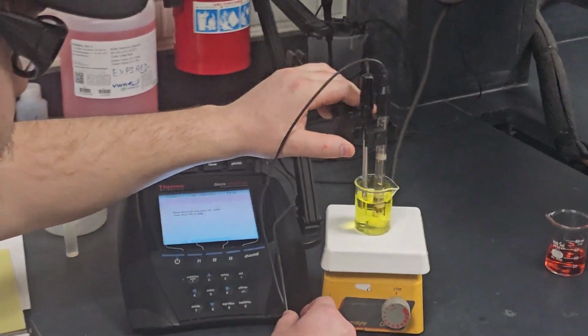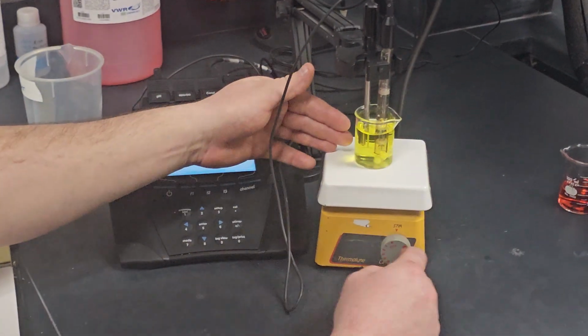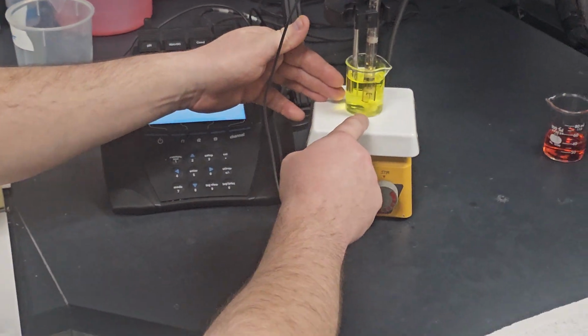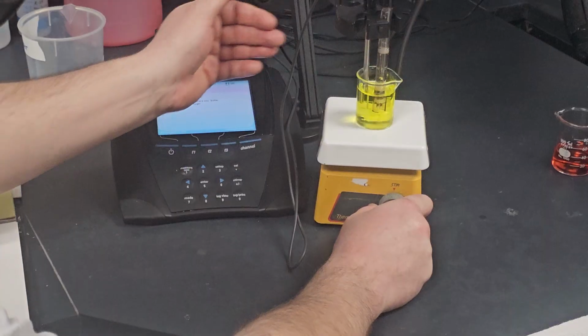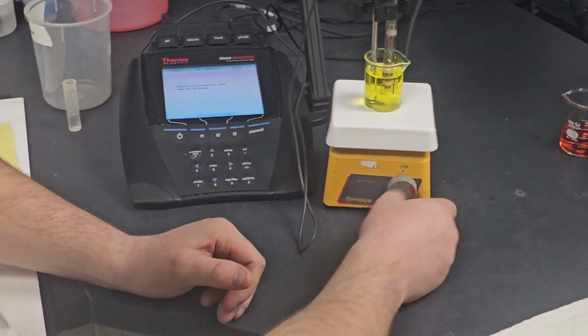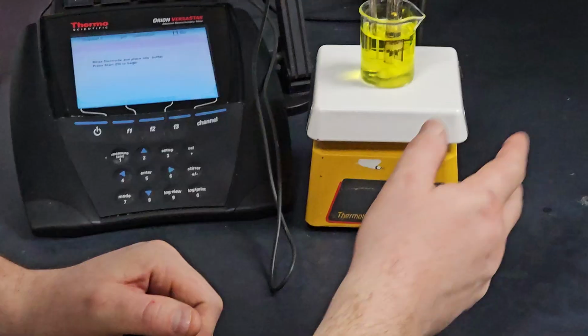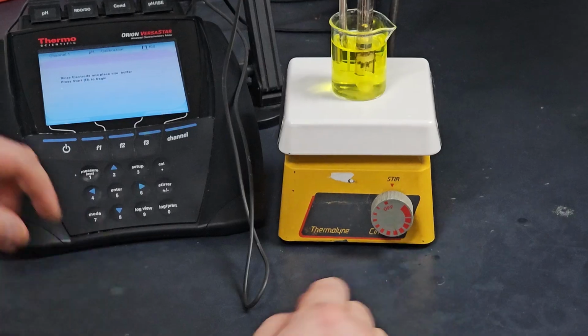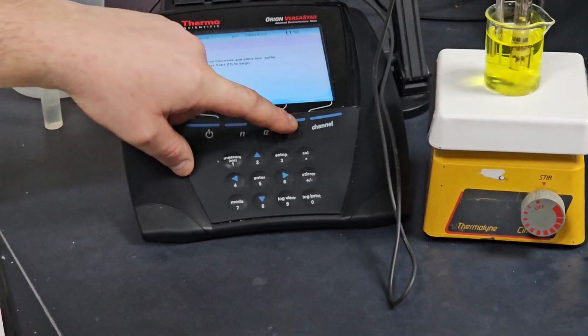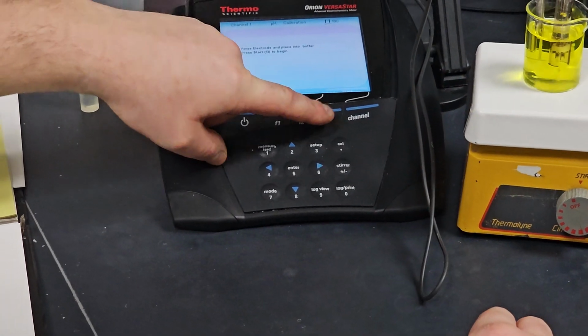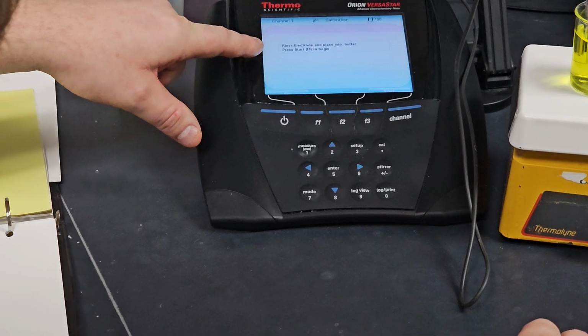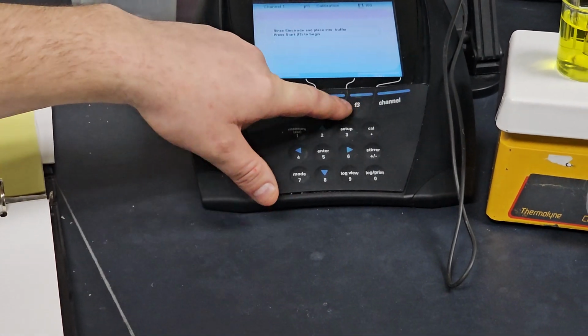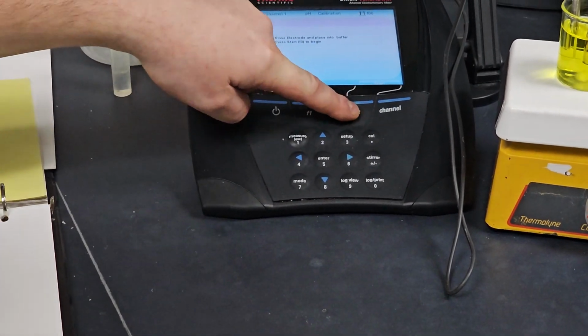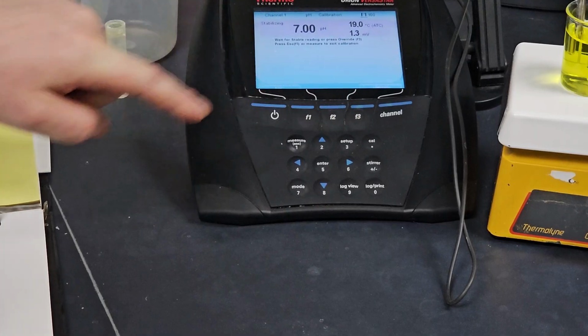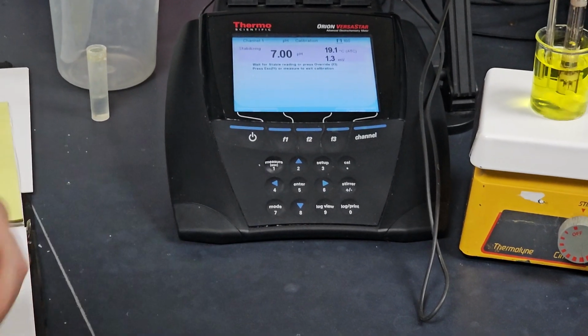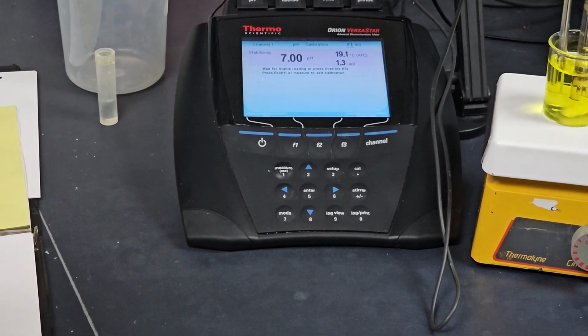Insert the probe. Make sure your stir bar is on. You can control the stir bar with this knob, but in general it should always be on. But make sure that it is on before you begin. So now we're ready to calibrate. We hit F3, which is the start button. And now it is reading the first buffer solution.